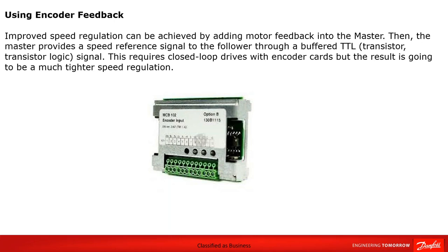As we've mentioned, how can we get better control? Well, we use encoders. So improved speed regulation can be achieved by adding motor feedback. We do this by the use of an encoder. Then that provides a speed reference signal to the follower through what we call a buffered TTL, which is a transistor-transistor logic signal. And this requires closed loop drives with an encoder card. So you have to have an encoder card fitted into the drive, but the result is going to be a much tighter, better control, better speed regulation.